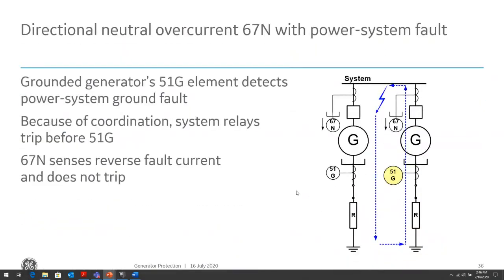The reason for having the directional ground overcurrent element is if you have parallel generators. So for a fault in, for example, the system bus, both generator ground overcurrent elements will see that fault and might trip both generators. So we won't be able to discriminate where that fault is. If a fault's on the left generator, same thing, the generator 51G will see that fault as well as the right side generator 51G, and again will unnecessarily trip its breaker for a fault outside of its zone of protection. So if you have a system like this where you have parallel generators, you might want to consider the 67N. What the 67N is, it's a directional element that looks at ground faults that are only flowing into that generator.